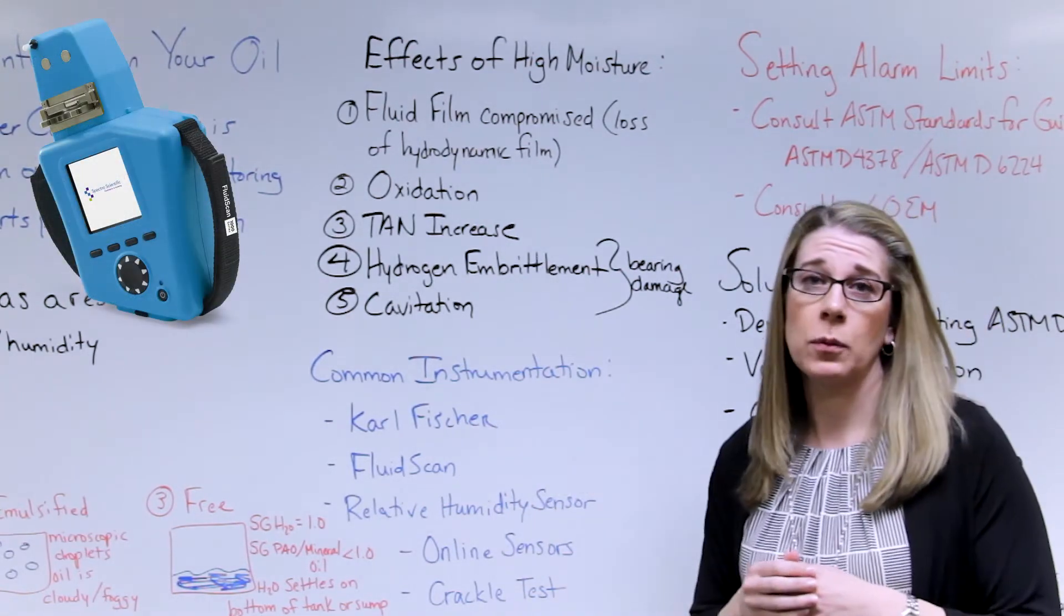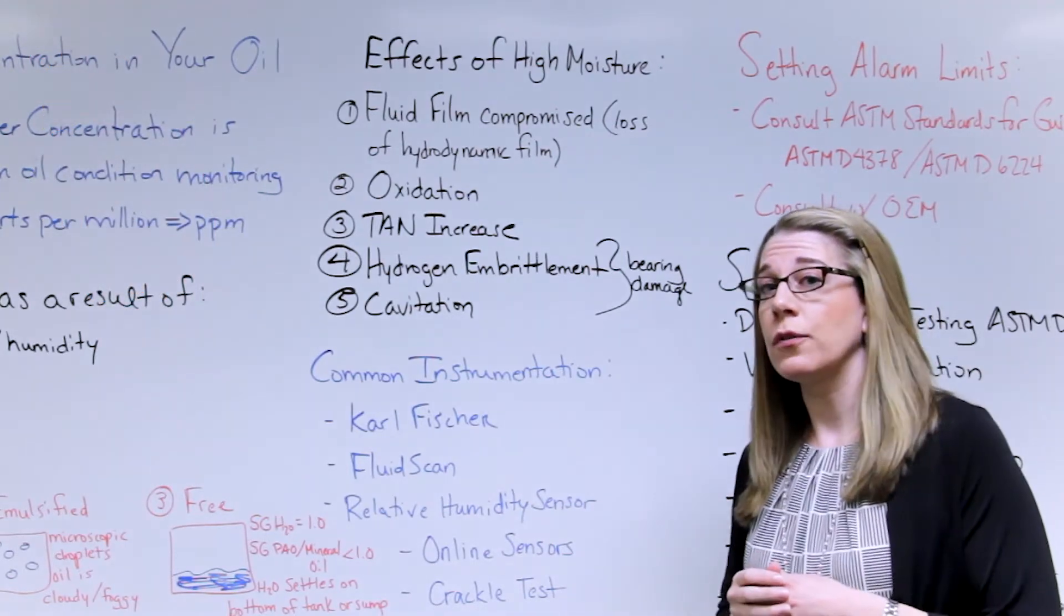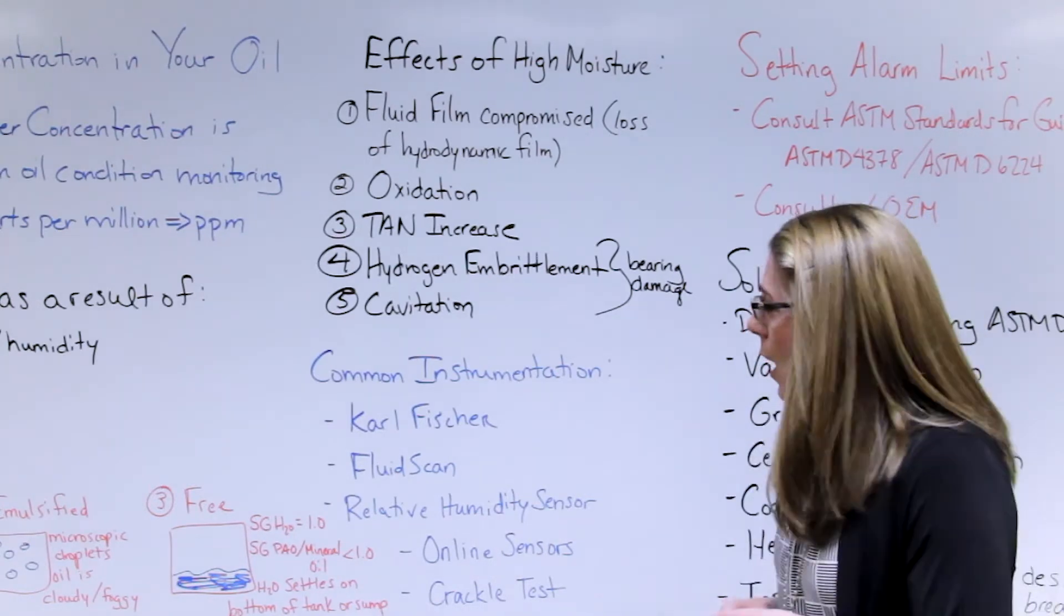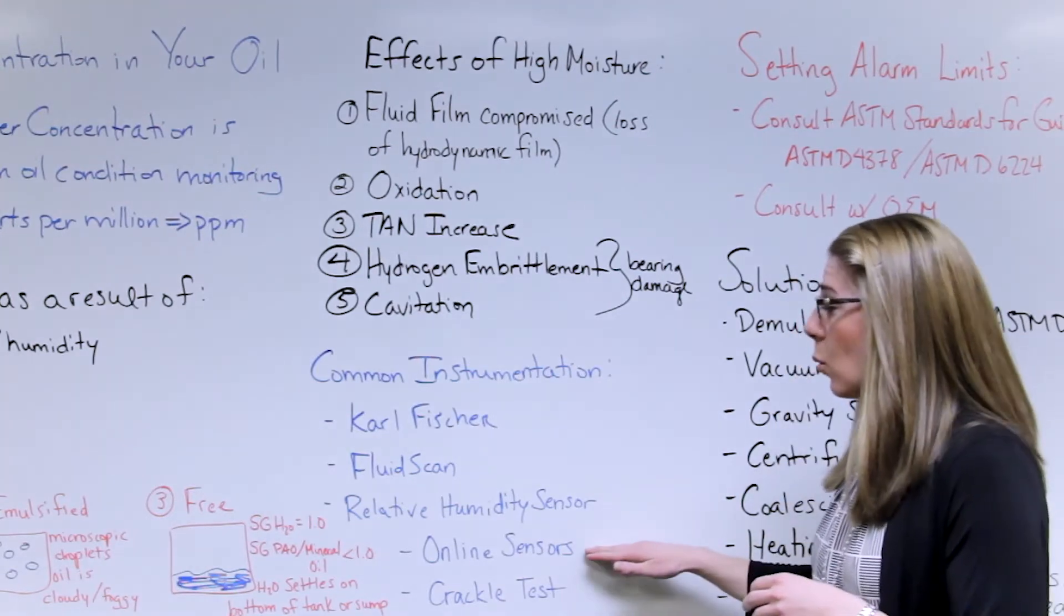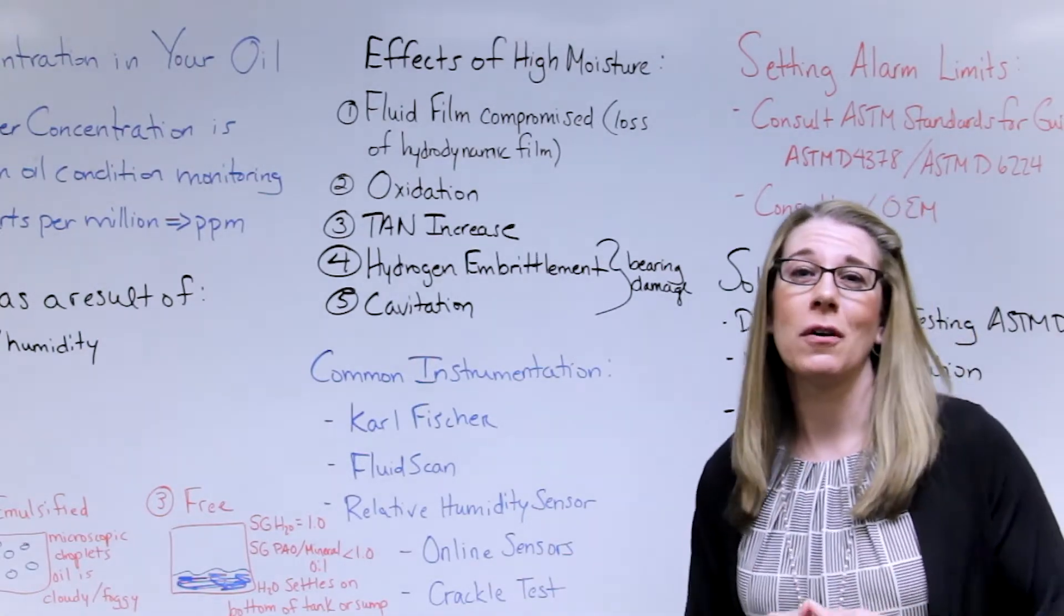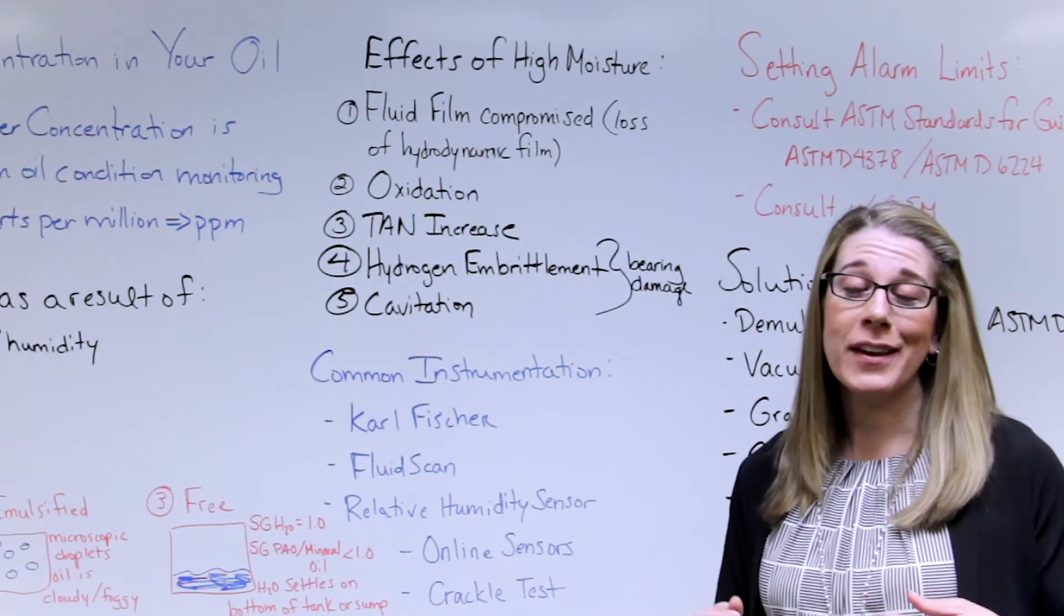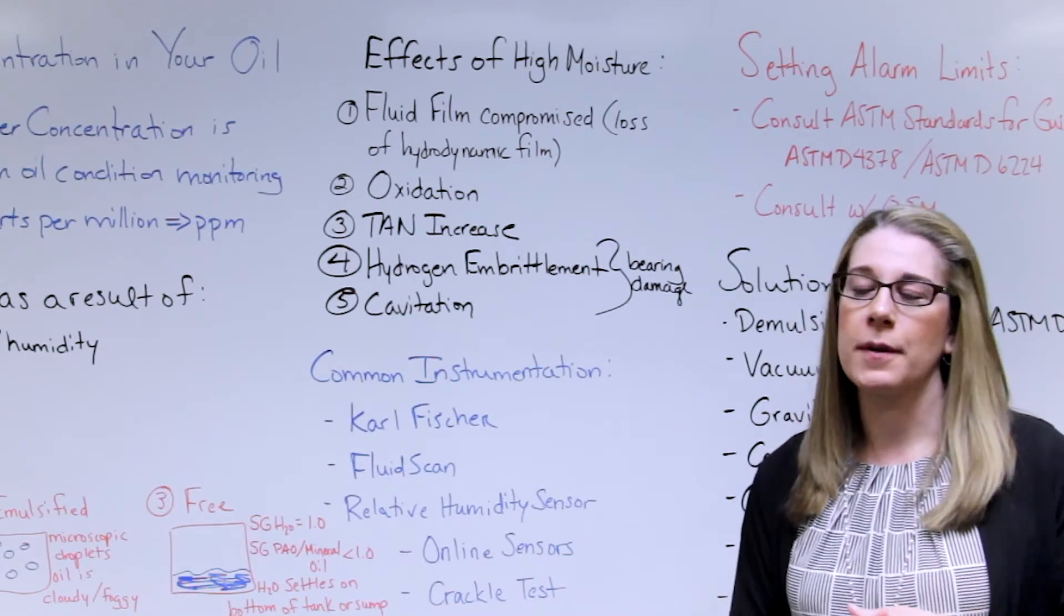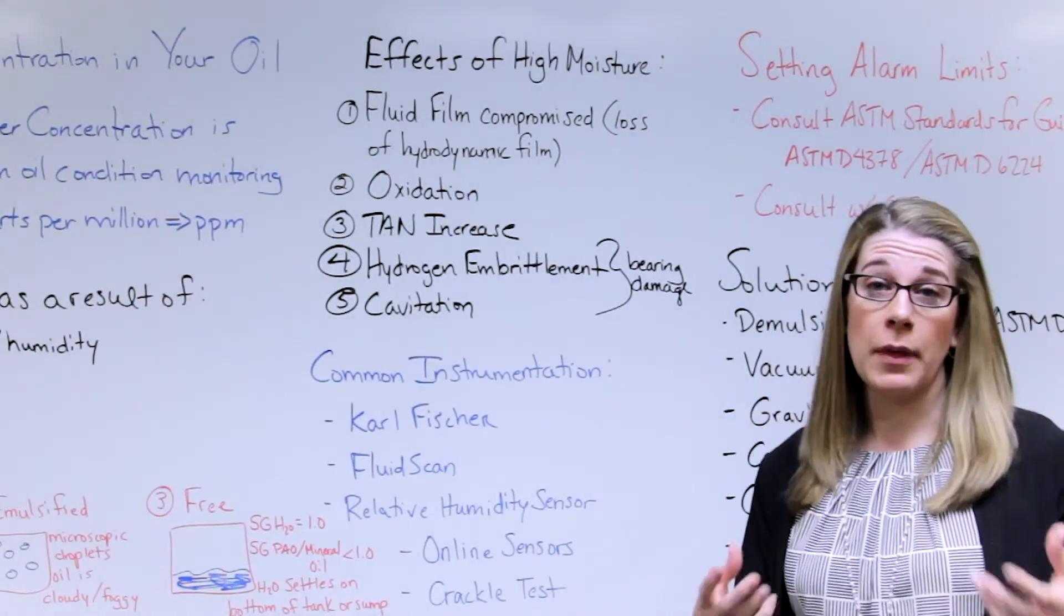Then we have the FluidScan device, which is part of our MiniLab system here at Spectro. This is an IR device which also measures parts per million and can be related back to the Karl Fischer method as well. I'm sure most of you have also heard that there are relative humidity sensors available. There's also online sensor technology. And then finally there's a very down-and-dirty method, if you will, of the crackle test. The crackle test is simply just dropping some oil on a hot plate, and you see how much it fizzes, and then you can correlate that to a parts per million. That's a pretty broad methodology. There's definitely some limitations with that, but in a pinch that works as well.